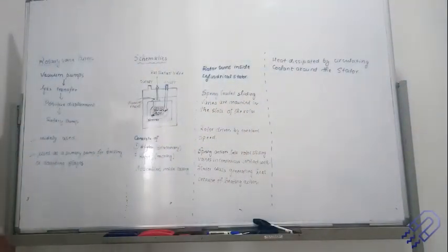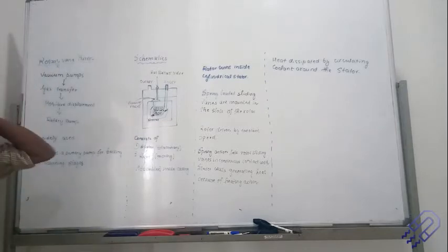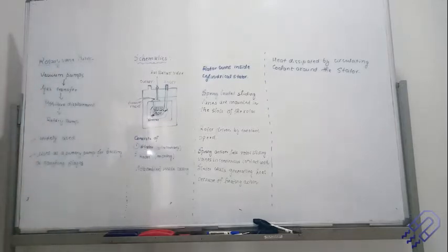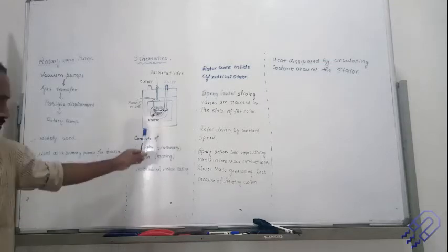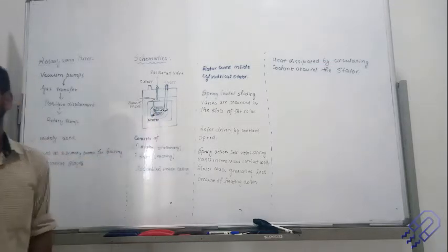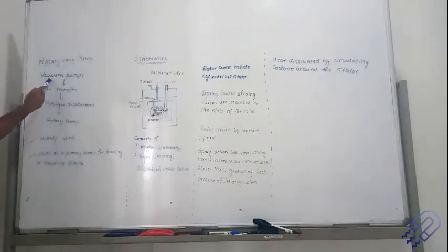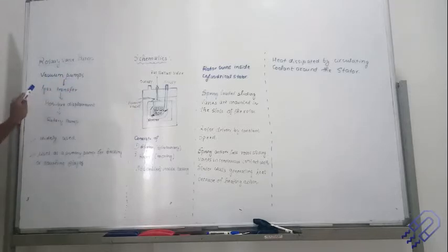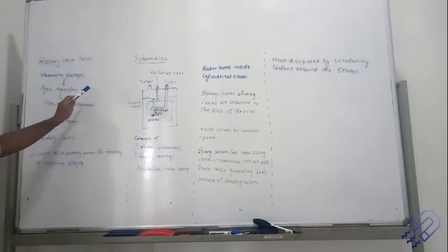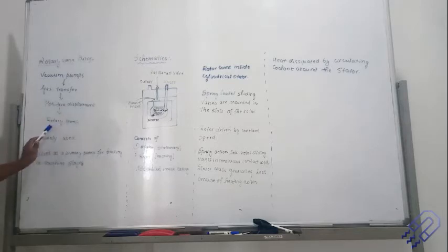We have a rotary vane pump. We are going to use a rotor stator system to drag out air. Looking at the table, we have vacuum pumps, and under this we have gas transfer and entrapment as the two types. For gas transfer, if it is positive displacement, we are basically having the rotary pump.